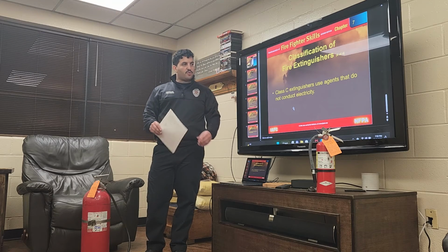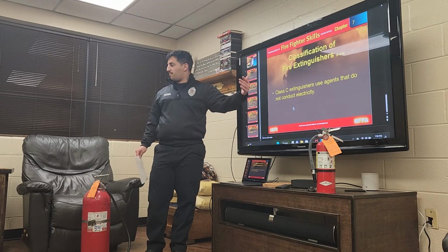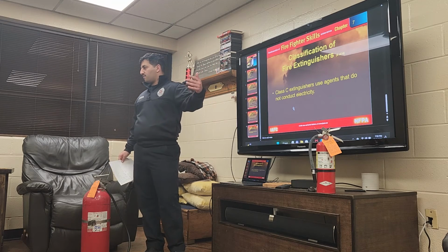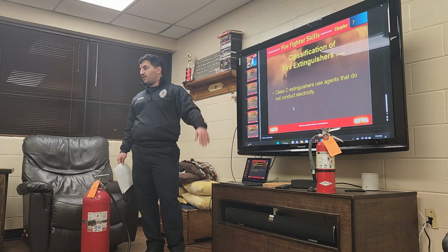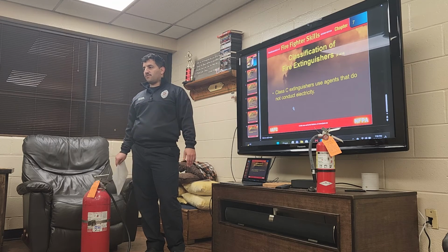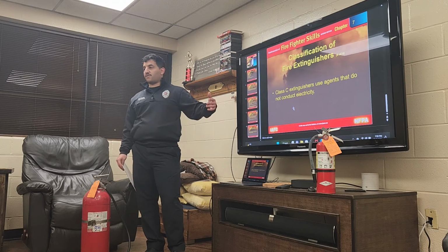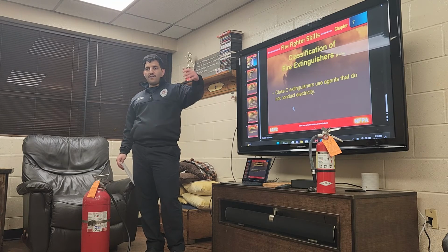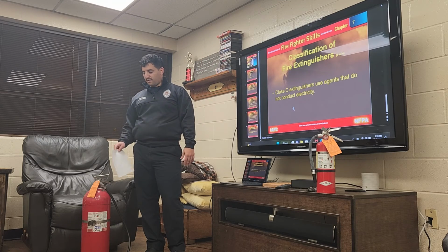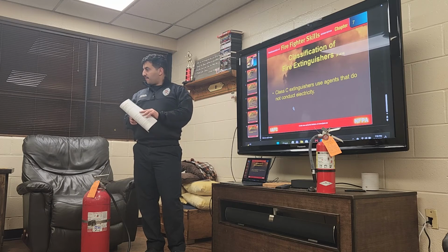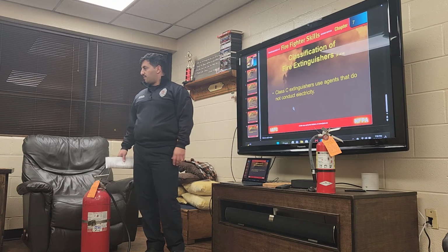Going back to how high you should have it above the ground, NFPA says it should be 3.5 to 5 feet above the floor, depending on the size of the extinguisher. And they have to be in accessible areas. You can't have it behind a trash can or something that people are going to have a hard time reaching in case they need it. Do you have to have one in the kitchen? You always have to have a fire extinguisher.